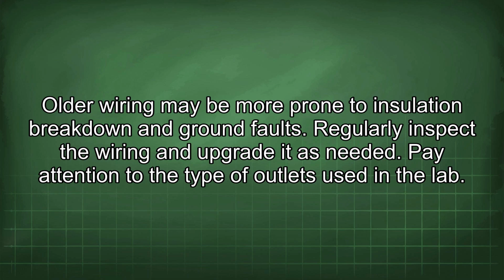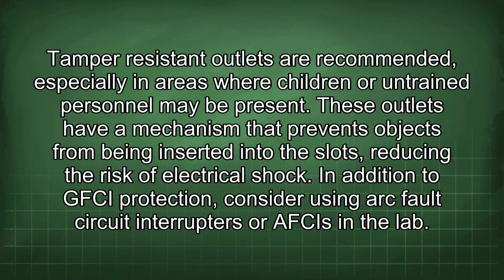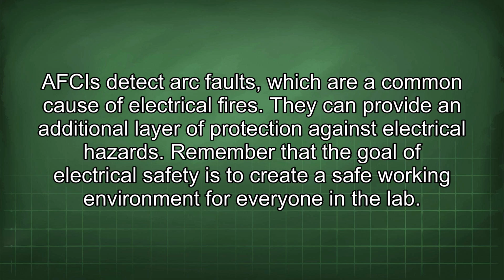Pay attention to the type of outlets used in the lab. Tamper-resistant outlets are recommended, especially in areas where children or untrained personnel may be present. These outlets have a mechanism that prevents objects from being inserted into the slots, reducing the risk of electrical shock. In addition to GFCI protection, consider using arc fault circuit interrupters or AFCIs in the lab. AFCIs detect arc faults, which are a common cause of electrical fires. They can provide an additional layer of protection against electrical hazards.